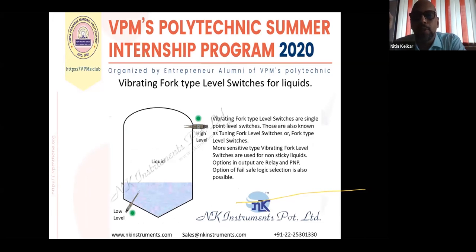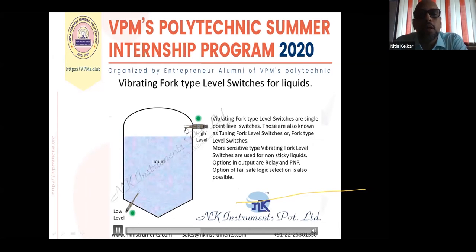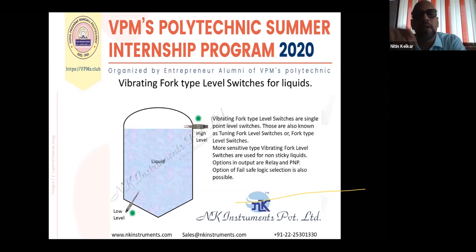When power is given to it, it will start vibrating, and these vibrations are transferred to the fork, which is two lightweight stainless steel plates, which will start vibrating. And when the liquid reaches this probe, the motion of the probe will be restricted by the presence of the liquid itself, and the switch will operate. This can be a PNP, that is a digital output type switch, or it can be a relay.